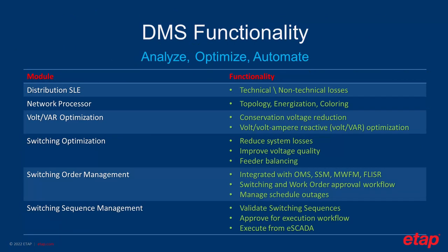In distribution, standout applications include distribution state estimation, where you can determine technical and non-technical losses. The network processor analyzes the topology, coloring the system based on energization and voltage levels. The Volt/VAR optimization (VVO) provides conservation voltage reduction and reactive power optimization, maintaining your voltage levels while determining the dispatch of reactive power resources. The switching optimization allows you to reduce system losses, improve voltage quality, and achieve feeder balancing through optimization of the system topology.